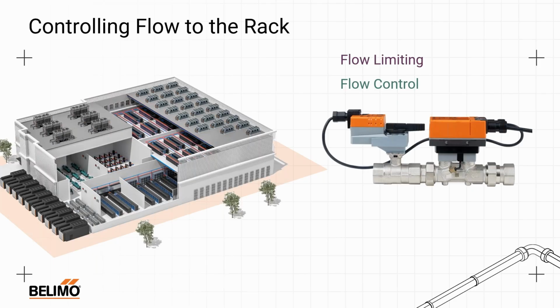From flow limiting, we can go to flow control. Flow control gives us exactly what it sounds like. We don't limit to a specific flow. We can control to almost any flow. So what's pictured here is a Belimo electronic pressure independent valve, but any pressure independent valve from any manufacturer would qualify as flow control. And that would give you the ability to have an automation system or some other form of control tied directly to it to prescribe what flow you would like to have going to the rack at any given point. The value in this type of control is obviously it gives us some versatility, and on some versions we're going to get some feedback.